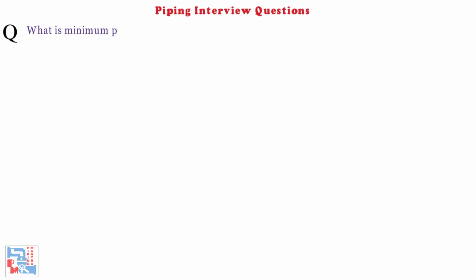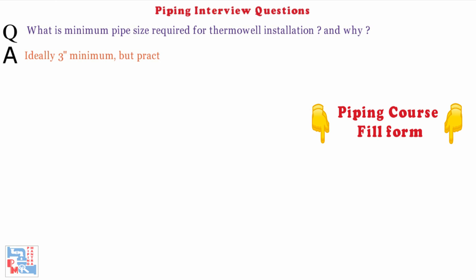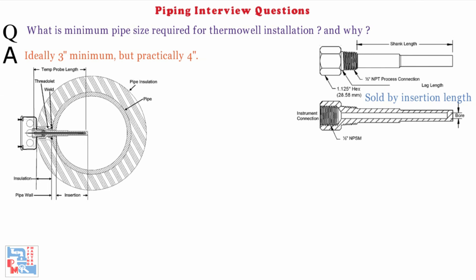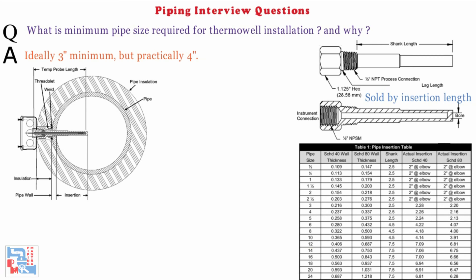Question 1: What is the minimum pipe size required for the thermowell installation and why? Ideally 3 inches minimum but practically 4 inches. Because thermowells are sold by insertion lengths, which is the length of the thermowell inside the pipe. The right length for a thermowell largely depends on the diameter of the pipe or tube. One rule of thumb is to insert a thermowell anywhere from 1/3 to 2/3 of the way into the fluid stream.